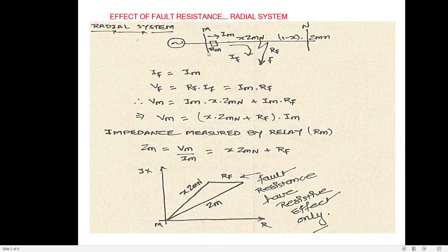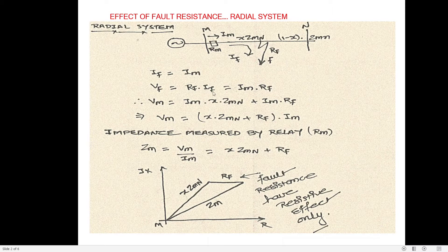The fault point voltage VF equals RF × IF. Since IF equals IM, VF equals IM × RF. The voltage measured by relay RM is IM × X·ZMN plus VF, which gives VM = (X·ZMN + RF) × IM. The total impedance measured by relay RM is VM divided by IM, which equals X·ZMN + RF.